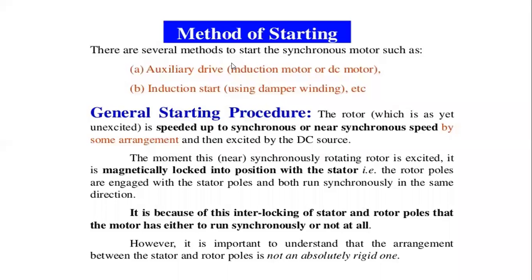By using the auxiliary drive we start the motor, or by using the induction torque we start the motor. Auxiliary drive means an induction motor or a DC motor, and induction torque means using damper windings.